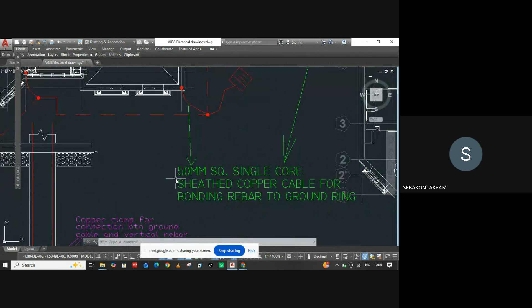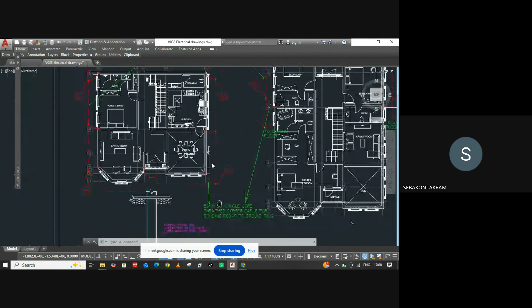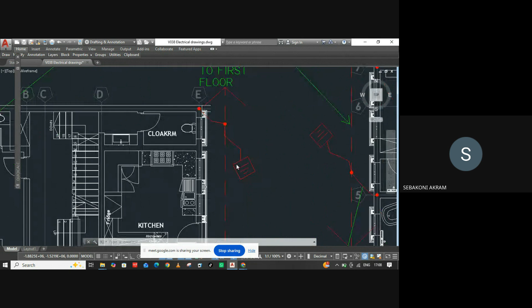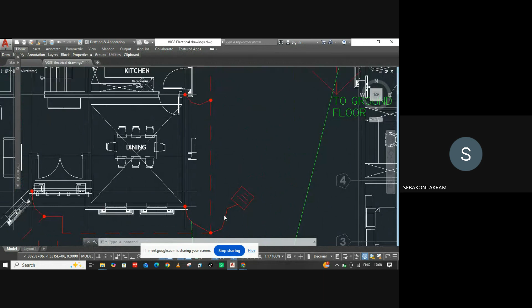We do have, first of all, this is a ring. It's called a ring method of earthing. Connecting like a ring on the side of the building, so that you connect the rebars. You connect the rebars to that ring that is really earthed, having earthing rods at different points.